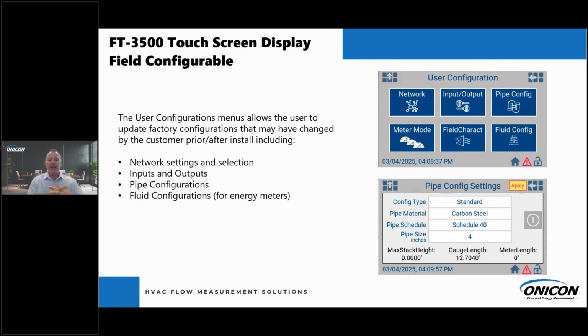So you can see in the bottom right-hand corner of the screen, the pipe configuration settings. Say you ordered it for a 6-inch, and once you got it out in the field, you realize it's an 8-inch pipe. You can quickly go in there and change the settings, and you're not messing with the calibration because it's a velocity measurement. So you're not messing with the calibration when you do those changes. Great added feature that we have there.